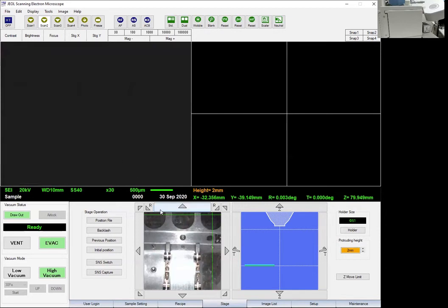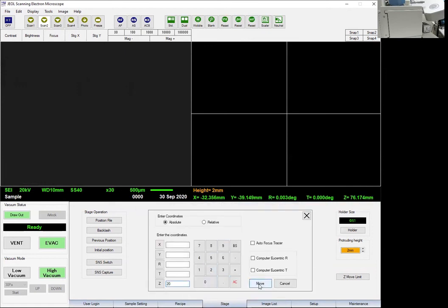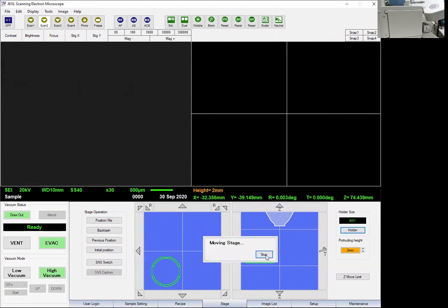The next thing we're going to do is to move the sample up so it's about the right distance from the electron column. In the end, the sample should be 10 millimeters below the electron column. But we're going to move it up carefully because the last thing we want to do is to break anything. Okay? So now it's moving the stage up. And this should stop at about 20 millimeters away, and then we can do the rest by hand. There's another camera, which you can't see in this image, which is showing me the sample holder slowly moving up inside of the instrument, just so I can stop in case there are problems.